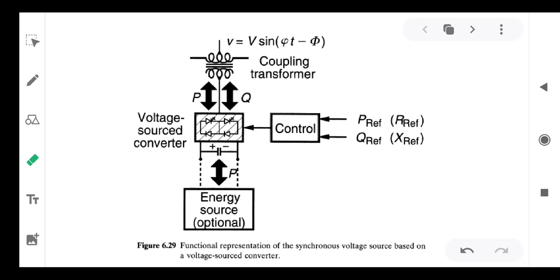If you look at this figure, this is the line. In series with the line, so this is SSC. So this SSC is connected in series with the transmission line. So this is the coupling transformer connected in series with the transmission line. The primary is of high voltage side, secondary is of the low voltage side. Low voltage side, VSC is there, voltage source converter, which acts as SSC.